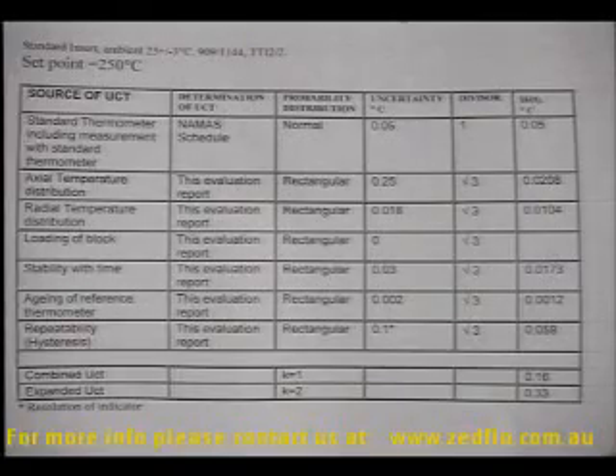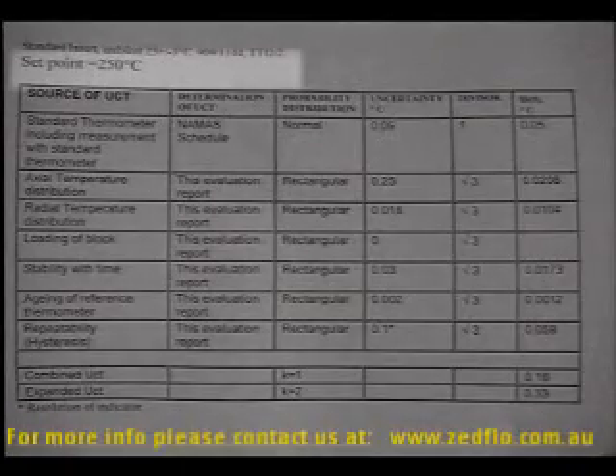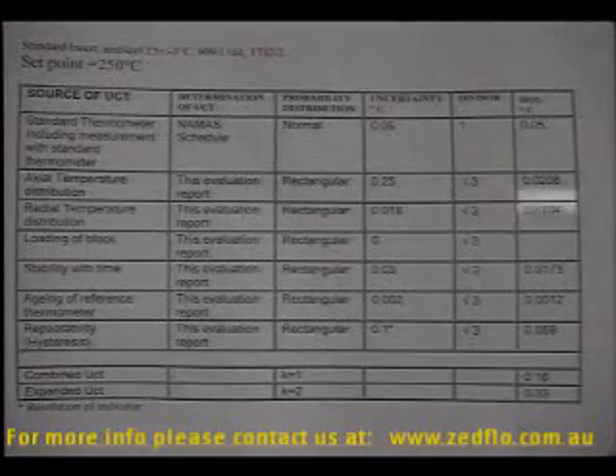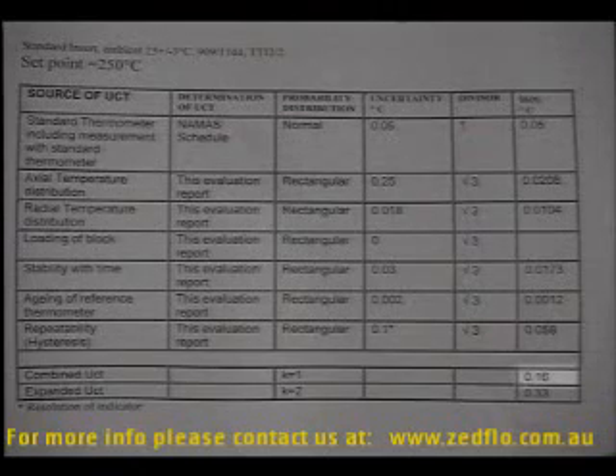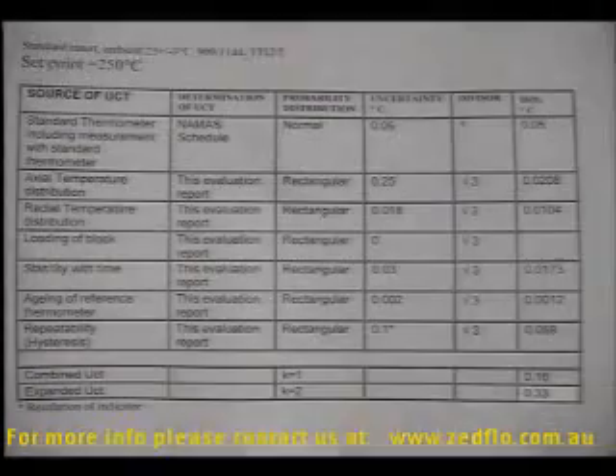We are right at the temperature limit of one of the products, and if we add up and combine all the uncertainties, we get an uncertainty of about 0.16 degrees Celsius. We double that to give us a 95% confidence level, and we get an uncertainty of plus or minus about 0.33 degrees Celsius. This is worst case, and we can make some other measurements that realistically show the kind of errors that we might expect with good procedures.